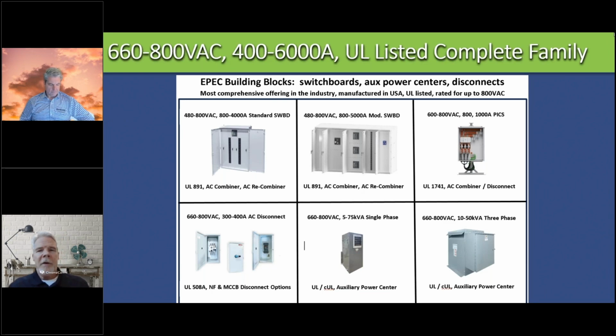Then over on the right-hand side, top right, we offer a fused disconnect that's also rated at 800 volts. And then down below, bottom left, we have a disconnect switch. So if you're not doing virtual central, if you have your inverter in the field, you can have a local disconnect that's rated at 800 volt as well, both a non-fused and a circuit breaker style disconnect. And then finally, the middle bottom and the right bottom are various types of aux power centers for either single phase or three-phase loads, taking your 690 volt in and producing 120/240 on the single phase, or maybe tracker power and 120/240, both if required on the three-phase units. Next slide.